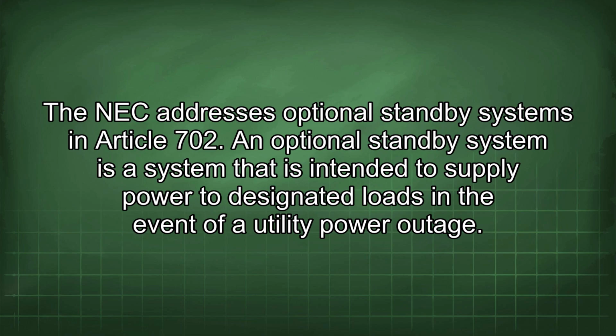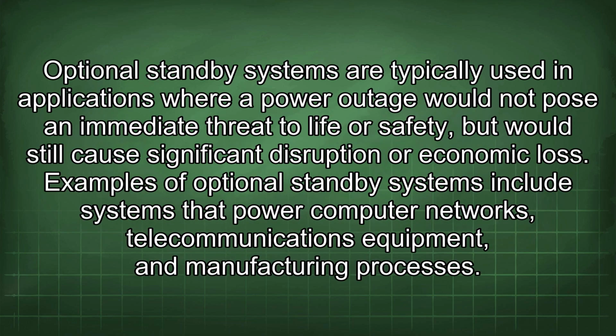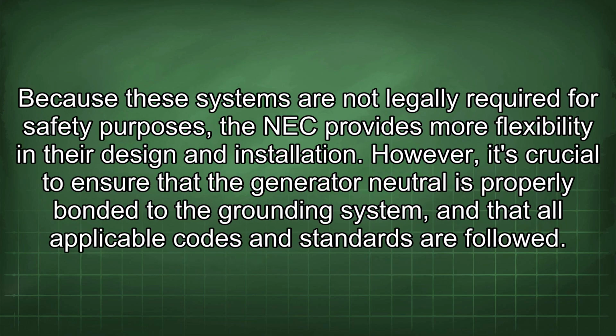The NEC addresses optional standby systems in Article 702. An optional standby system is a system that is intended to supply power to designated loads in the event of a utility power outage. Optional standby systems are typically used in applications where a power outage would not pose an immediate threat to life or safety, but would still cause significant disruption or economic loss. Examples of optional standby systems include systems that power computer networks, telecommunications equipment, and manufacturing processes. Because these systems are not legally required for safety purposes, the NEC provides more flexibility in their design and installation. However, it's crucial to ensure that the generator neutral is properly bonded to the grounding system and that all applicable codes and standards are followed.